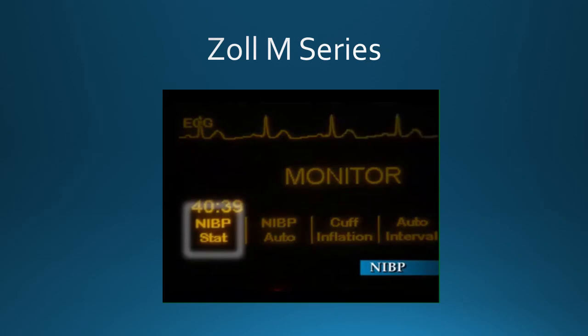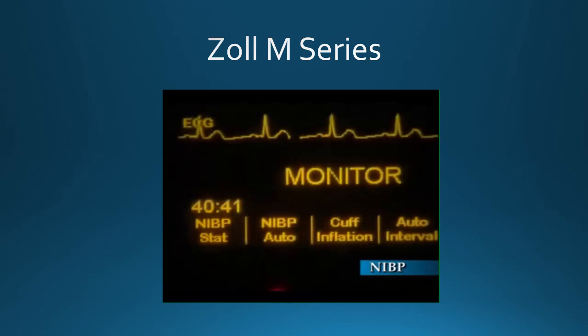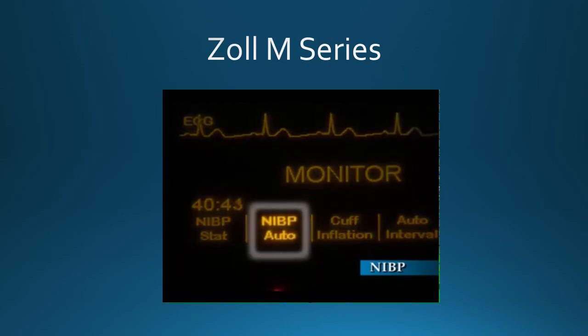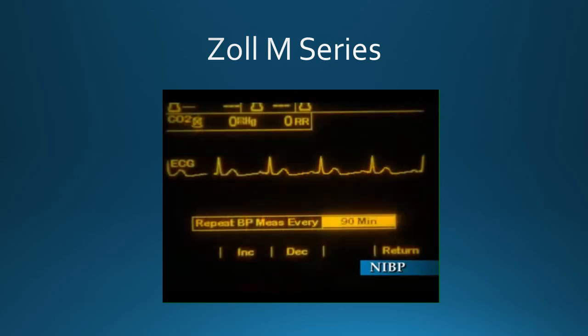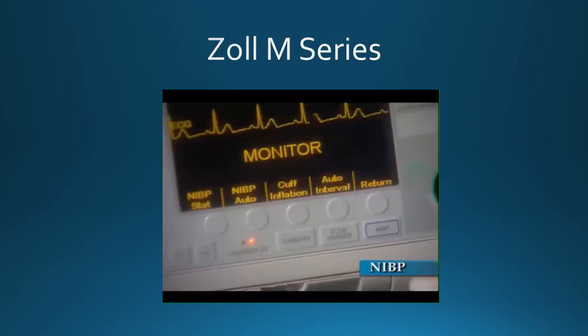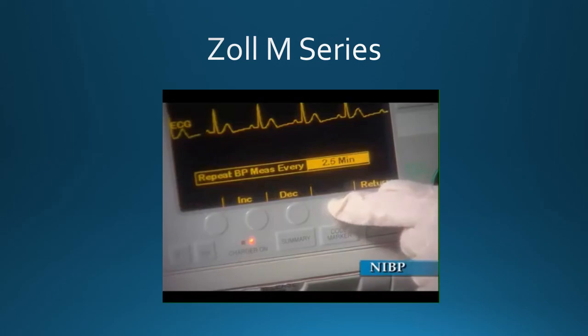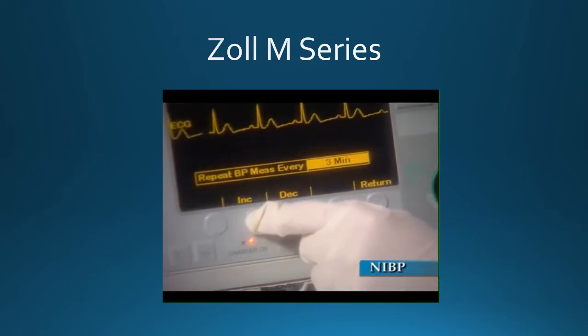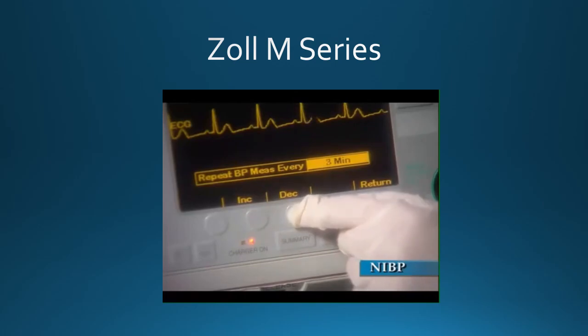NIBP Stat allows users to take up to 10 readings within 5 minutes. NIBP Auto allows users to take automatic measurements at preset increments. These increments can be set between 120 minutes and 2.5 minutes. The settings can be easily changed by pressing the Auto Interval soft key and pressing the Increase or Decrease soft keys to adjust the settings.